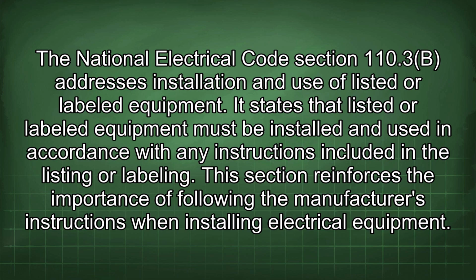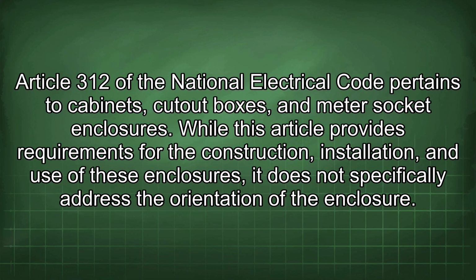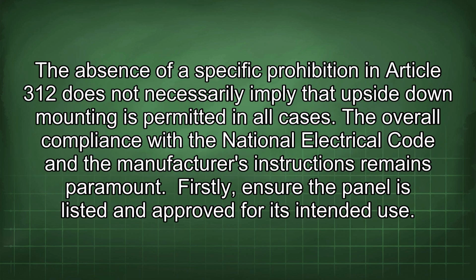The National Electrical Code Section 110.3(B) addresses installation and use of listed or labeled equipment. It states that listed or labeled equipment must be installed and used in accordance with any instructions included in the listing or labeling. This section reinforces the importance of following the manufacturer's instructions when installing electrical equipment. Article 312 of the National Electrical Code pertains to cabinets, cut-out boxes, and meter socket enclosures. While this article provides requirements for the construction, installation, and use of these enclosures, it does not specifically address the orientation of the enclosure. The absence of a specific prohibition in Article 312 does not necessarily imply that upside-down mounting is permitted in all cases. The overall compliance with the National Electrical Code and the manufacturer's instructions remains paramount.